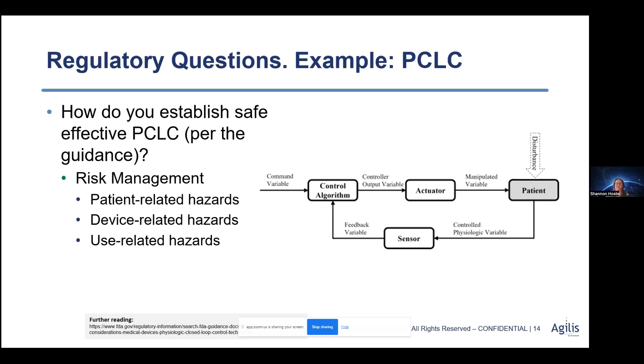And then from there, understanding the risk, you move into device design, you move into verification and validation testing, non-clinical testing, and then they discuss human factors testing as well, and then labeling. And some of the interesting things they mention when they talk about human factors is specifically that your human factors testing should be designed to capture automation-related hazards, so complacency, automation bias, et cetera. And that if you're labeling in the instructions that the user needs to recognize an emergent unsafe situation and intervene, right? So when does that user need to be paying attention, and when do they not need to be paying attention? If you're relying on telling them that in your labeling, then you need to show that that's an adequate risk control measure. So they're really focusing in on the potential risks associated with a specific situation and automation, and understanding that our mitigations within our systems are safe for that.